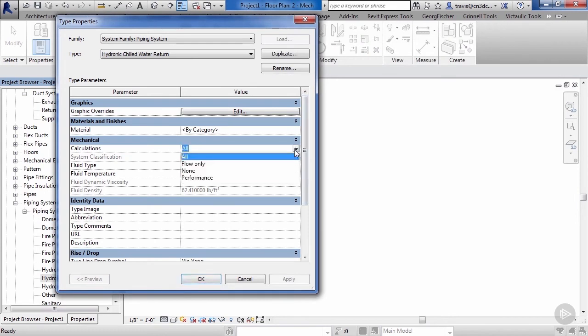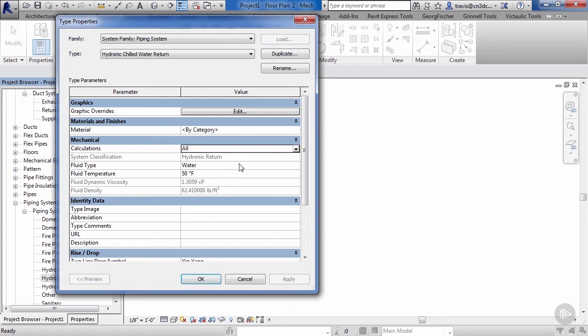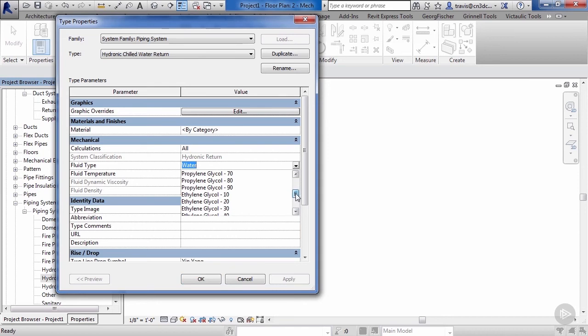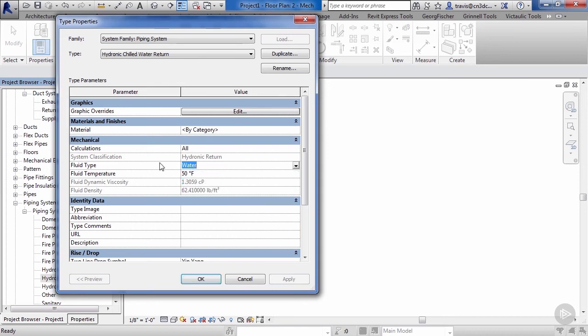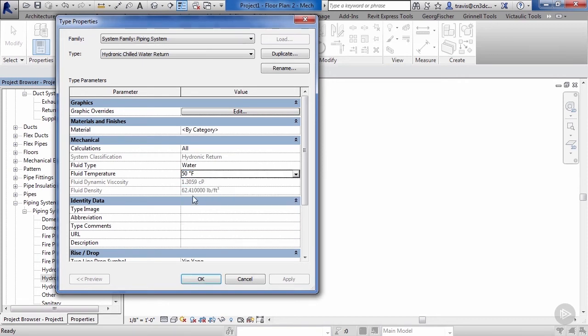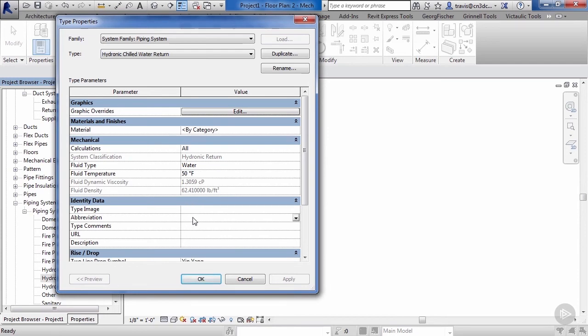Next we can apply calculations. We can go flow, none, or performance. We'll go ahead and just leave that. Our fluid type—we can decide what kind of glycol we want to use. Just leave that at water for now. Next we can decide on the fluid temperature. We can go all the way up to 220 down to 30 degrees. We'll just leave it at 50 for this example.